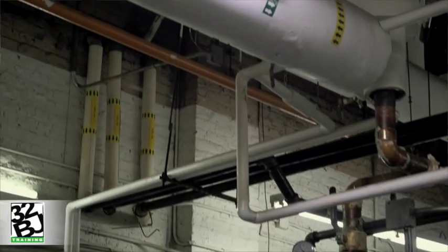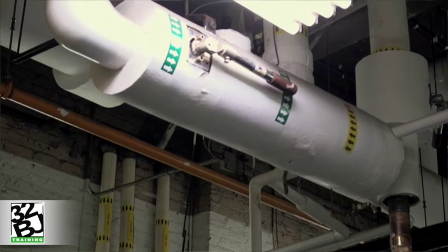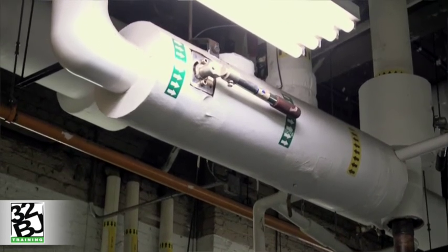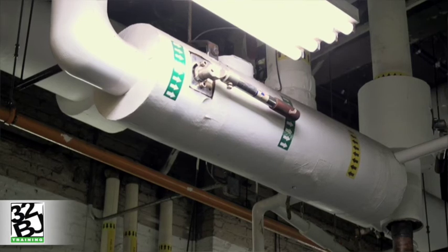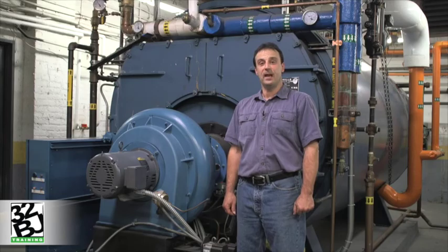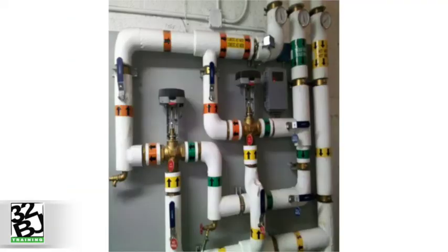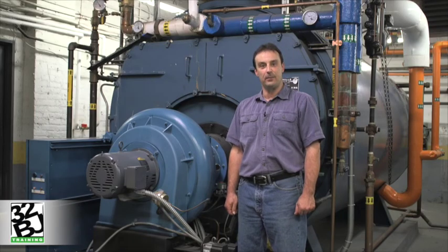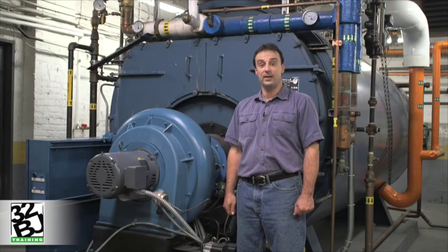At the mixing valve, hot water that has just exited the boiler is met with cooler water and mixed to provide 120-degree hot water leaving the mixing valve to provide throughout the building. Although there are different types of mixing valves, some mechanical in nature and some electronic, their purpose is the same: to reduce the domestic hot water temperature down to a safe temperature that can be used for domestic hot water.